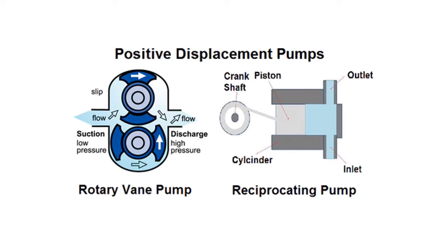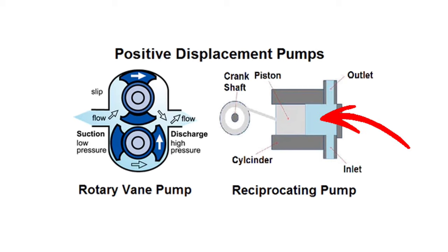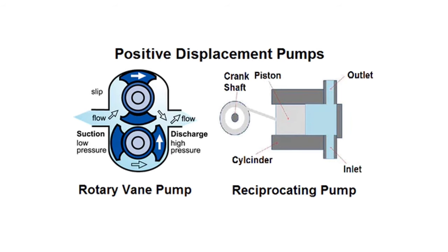Now let's shift our focus to positive displacement pumps. These come in two types: reciprocating — such as piston or diaphragm — and rotary — such as gear, vane, or screw pumps. Their key characteristic is displacing a fixed volume of fluid with each precise cycle, finding applications in oil and gas and food processing.